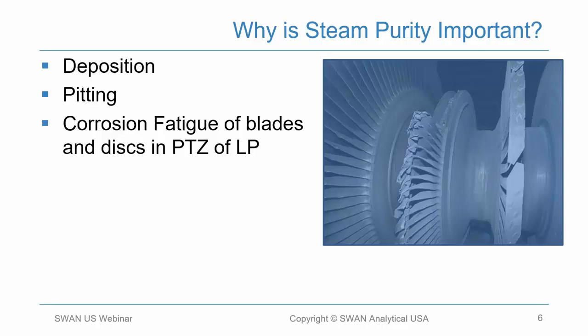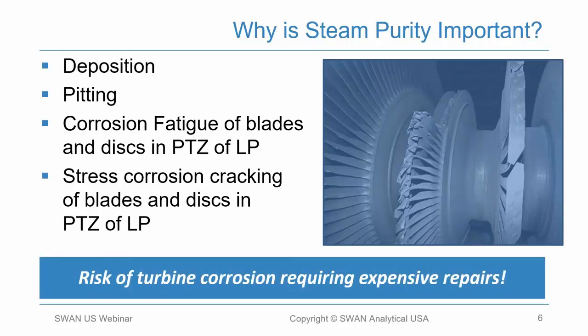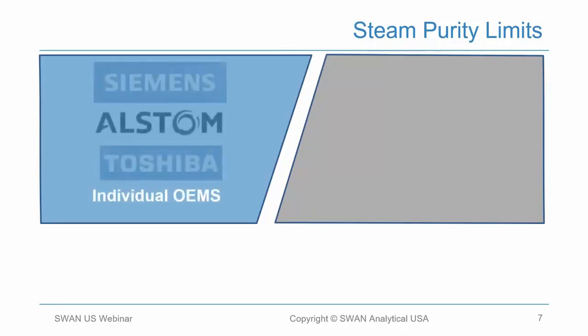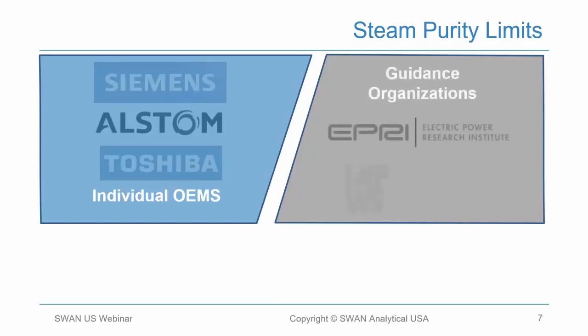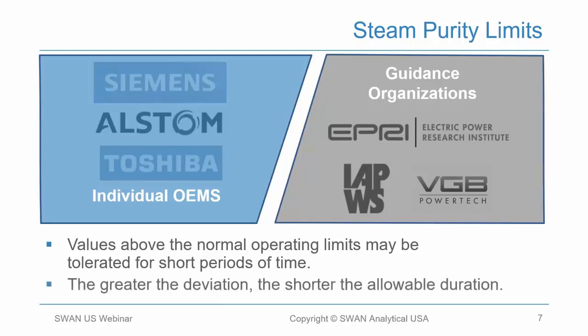Corrosive contaminants such as chlorides and sulfates can form deposits throughout the steam turbine. Those corrosive deposits lead to pitting during outage periods when the turbine is exposed to humid, oxygen-saturated air. When the unit is brought back online, mechanical stresses can cause cracks to form between those pits, leading to corrosion fatigue failure of blading and discs in the phase transition zone of the LP turbine, as well as stress corrosion cracking. The risk of turbine corrosion requiring expensive repairs is significant if steam purity is not meeting OEM and industry guidelines.